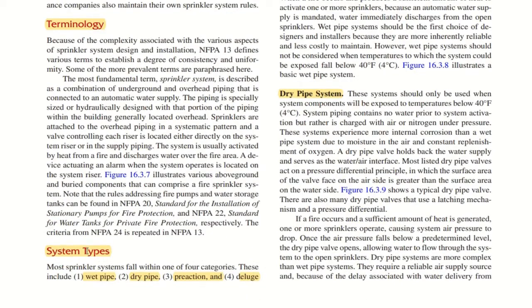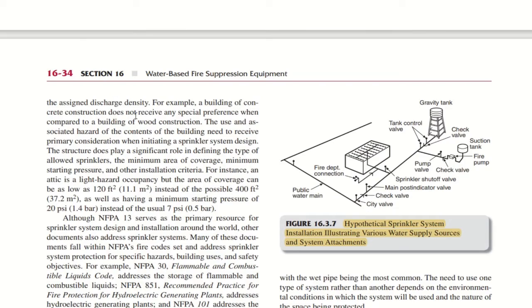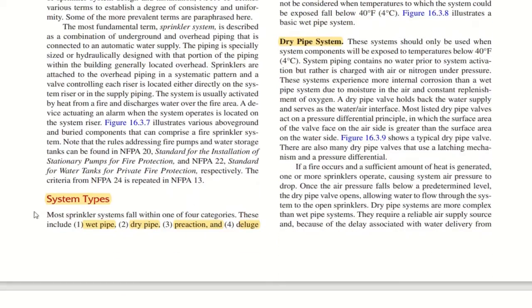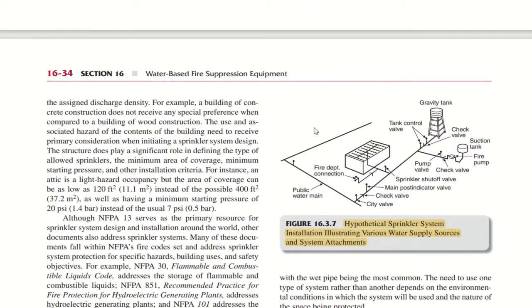Since chapter 3 is related to automatic sprinkler systems, it is focusing mostly on the types of sprinkler systems. We also covered this in the NFPA 13 course. You can go through that one, which is already available on my YouTube channel, Irfan CFPS. Here we go through the types of systems thoroughly. Most sprinkler systems fall into one of 4 categories: wet system, dry system, pre-action and deluge system. Here they have shown a network which will be serving the buildings from the city main and suction tank, gravity tank. They have taken the source.